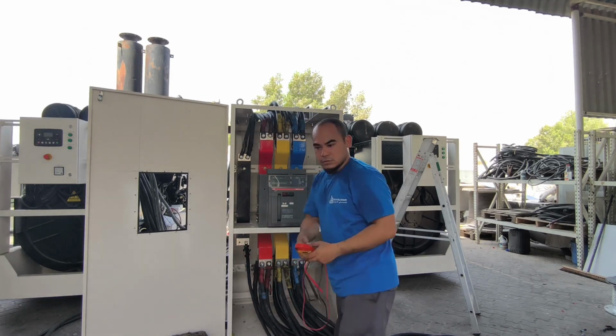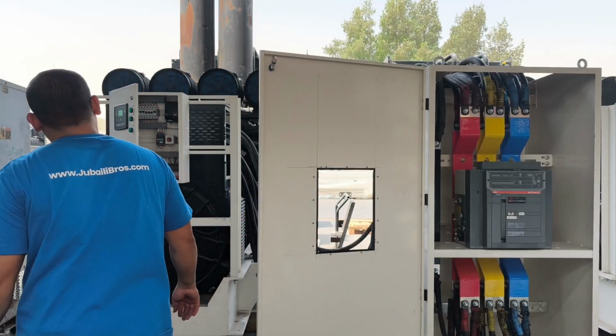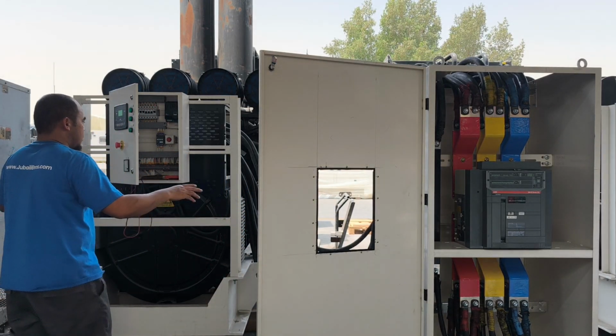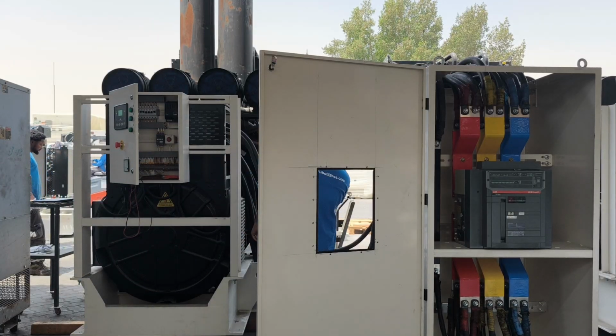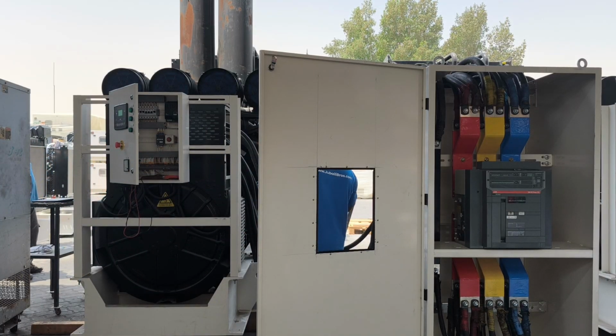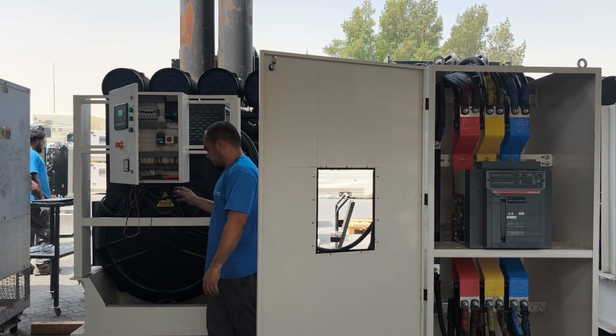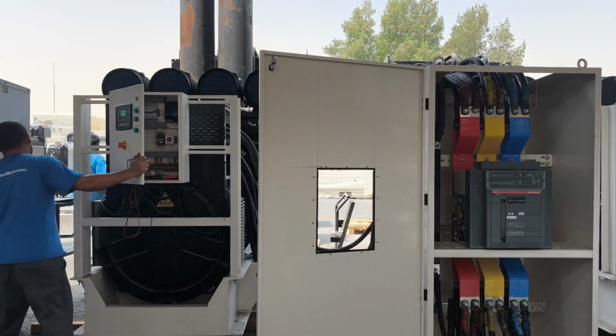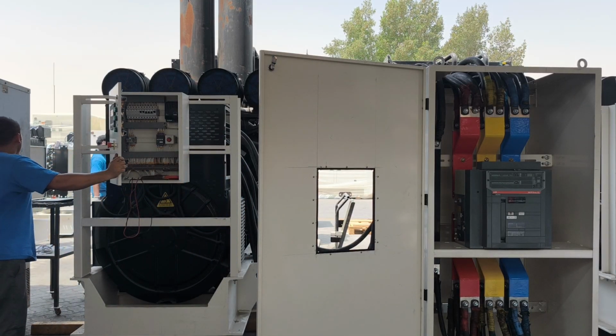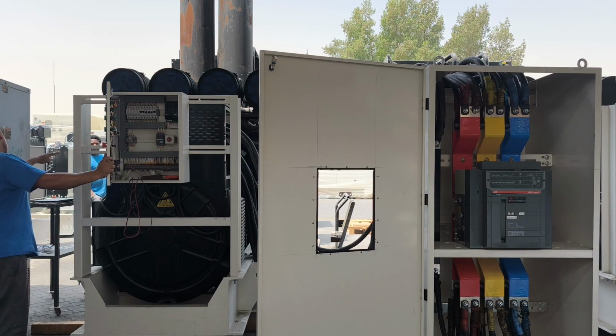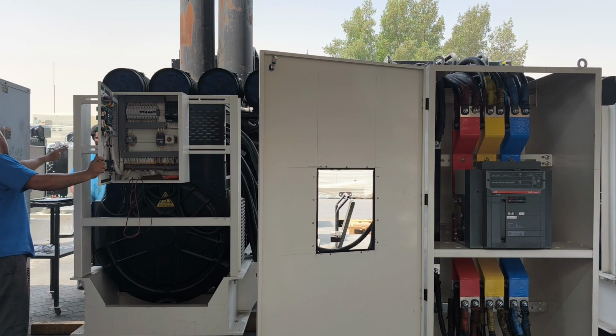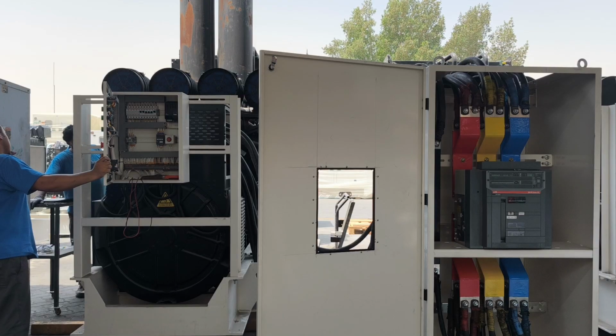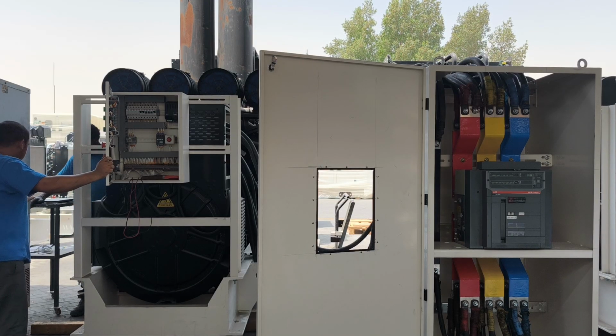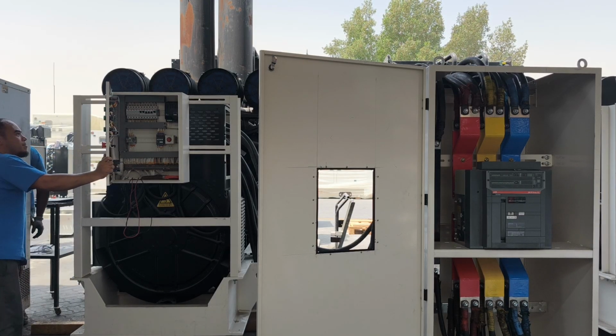So now I'm done testing the opening and closing of the breaker, so we are ready to start our generator. Before starting the generator, we need to double check if the fuel is connected, the oil is already there, and the coolant is already filled. We also need to double check all the wirings and the AVR to see if it is configured properly.